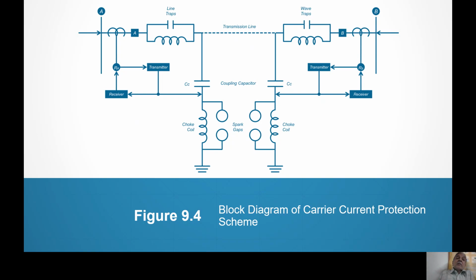Another equipment which you can see is the line trap. The line trap is a parallel resonant circuit of L and C. So what does it do? It allows the power frequency signal to pass through. It offers hardly zero impedance to the power frequency signal. But the carrier frequency signal, it will not allow to pass through. Otherwise, what will happen? The carrier signal sent from end B will pass through that, cross A and interfere beyond A. That is not required. The carrier has to work between A and B only. So the carrier signal is not allowed to pass.